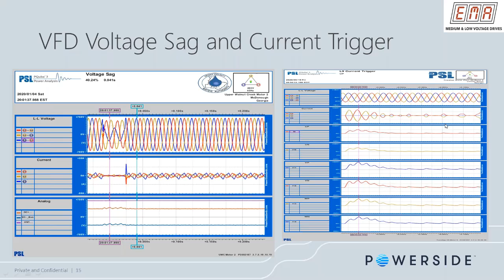However, if we lose power, that means the diode is not turning on, right? Or there's nothing to turn it on. I mean, there's no voltage for it to turn on. So therefore, the energy that is stored in the capacitor is what is being used by the drive. And as a result, you can see a ripple even on our low voltage power supply, and also on our DC buses here. This is our DC buses, as you can see. And then this is our line to line voltage, and this is our current, so at this point we are just losing current because of this problem.